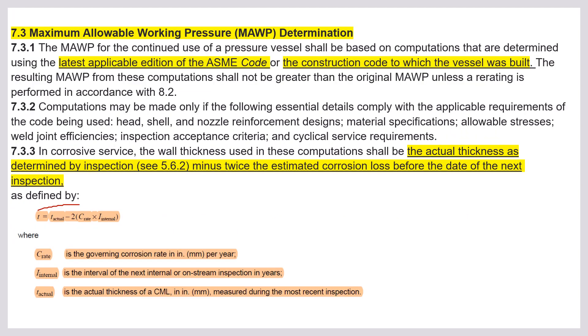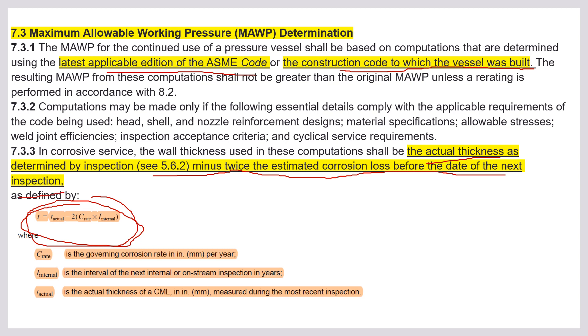Maximum Allowable Working Pressure (MAWP) determination is a question that usually comes as an open-book question. The MAWP for continued use of pressure vessels shall be based on computations determined using the latest applicable edition of the ASME code or the construction code under which the vessel was built. The actual thickness determined by inspection, minus twice the estimated corrosion loss before the date of the next inspection, is used. Here, t_actual is the actual CML thickness, I_internal is the interval to the next on-stream inspection, and C_rate is the governing corrosion rate — used to find the minimum required wall thickness.